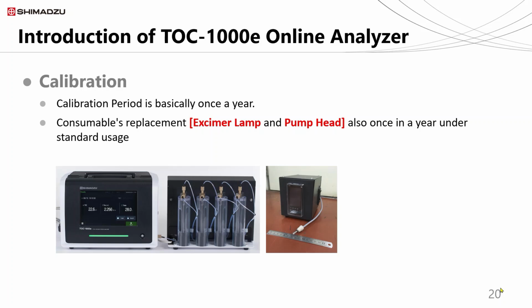Calibration period is basically once a year, but it depends on sample conditions as well. We cannot guarantee this period. But some users want it to be calibrated more frequently, like every 6 months. In this case, it's okay, no problem. Calibration frequency can be decided by the user.